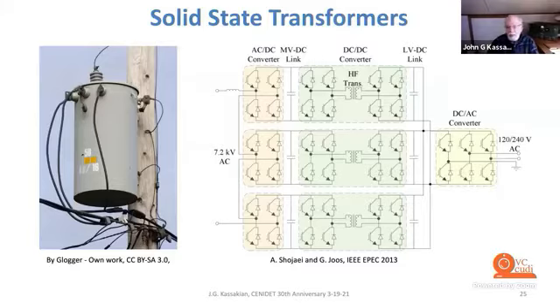On the right, you see a schematic of one manifestation of a solid state transformer. All a solid state transformer does is take AC at one voltage and frequency - in this case 60 hertz - convert it to a high frequency, transform the voltage levels through high frequency transformers, then down convert that voltage and frequency to the line frequency required, again 60 hertz. So you start out at 7.2 kV AC at 60 hertz and wind up with 120 volts at 60 hertz, with a transformer that is much smaller and much more efficient than the one on the left.